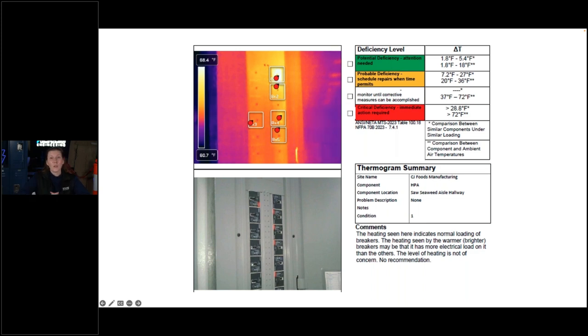Plus it's under normal loads, so the cooler, more purple parts aren't supposed to be warming up. But with electricity there's always some heat expenditure under normal operating conditions, even to this level. So the heating isn't of concern, and no recommendation is needed. Again, you need somebody with a camera who actually knows what they're looking at and all the parameters involved with a proper infrared scan.